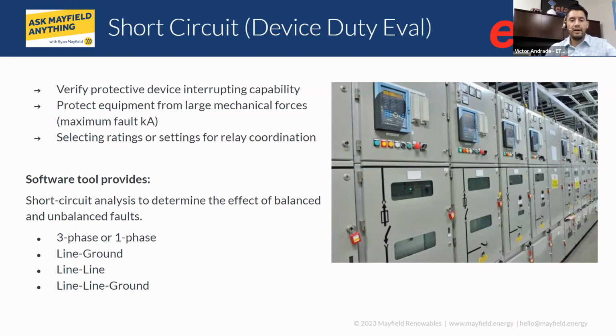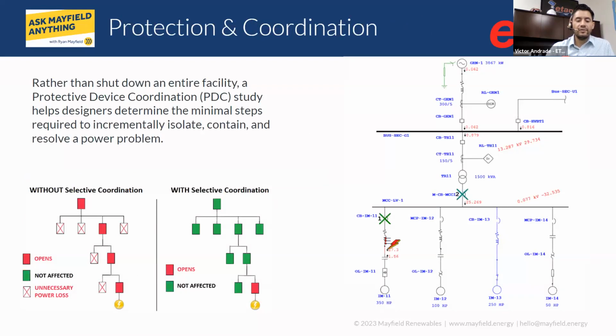All right, and let's talk about now the protection and coordination, which kind of ties into short circuit. So after we perform a short circuit study, we do protection and coordination. In fact, some larger utilities have an engineer that does protection, right? Their title is protection engineer. And the purpose of doing a protective device coordination, or PDC study, is to add reliability, isolate or contain the fault in the event that we have a short circuit. So if we look at the picture on the bottom left, you could see a system without selective coordination.